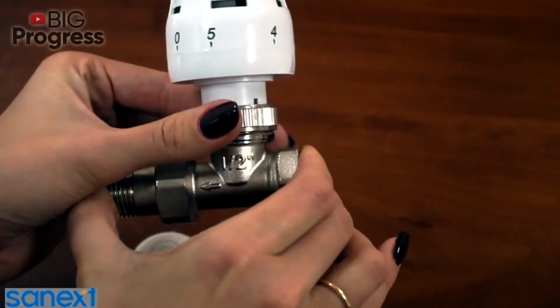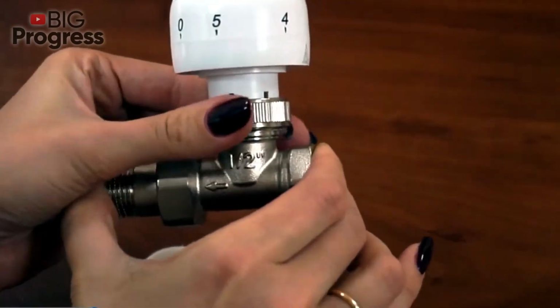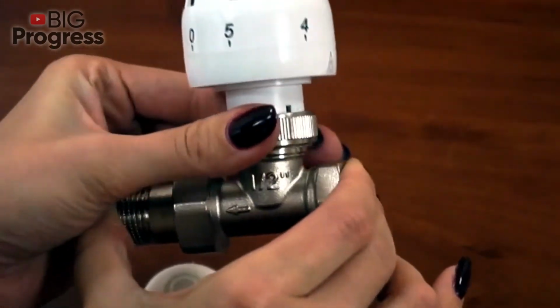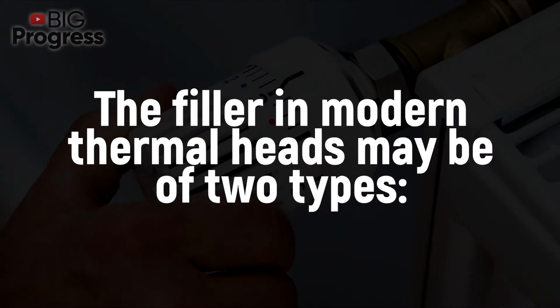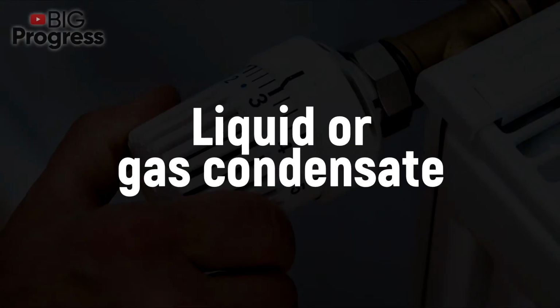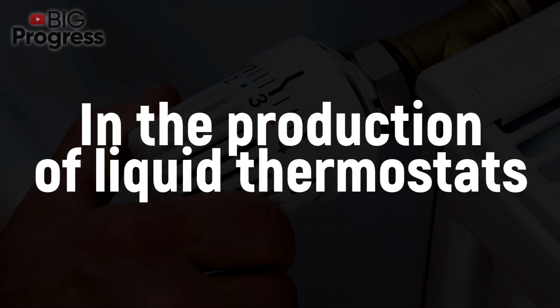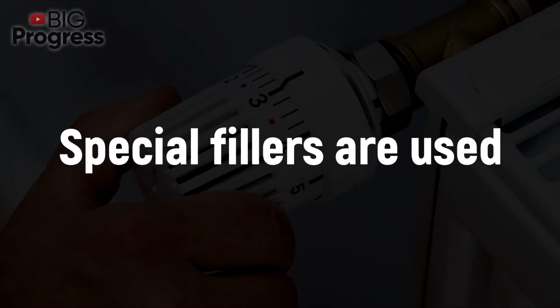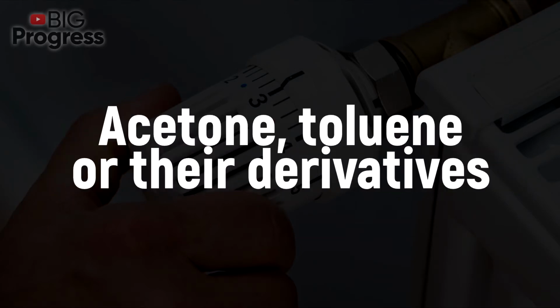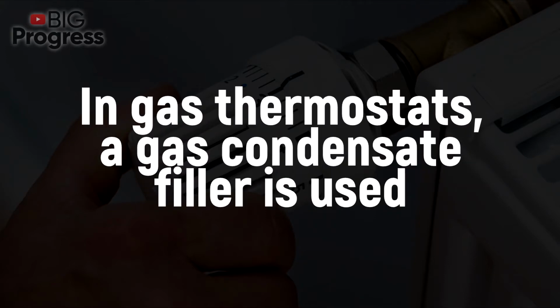In the middle of the thermal head, there are special bellows filled with a medium that is thermally sensitive to changes in the ambient air temperature. The filler in modern thermal heads may be of two types: liquid or gas condensate. In the production of liquid thermostats, special fillers are used: acetone, toluene, or their derivatives. In gas thermostats, a gas condensate filler is used.